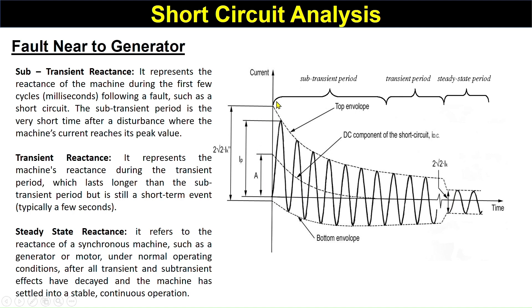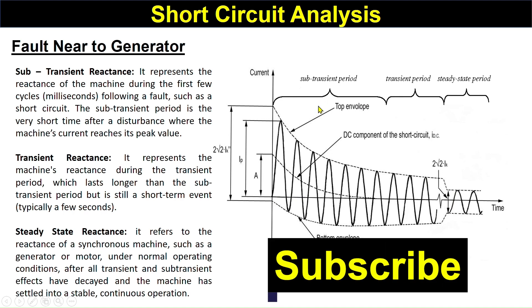The sub-transient period is the very short time of the disturbance where the machine current reaches its peak value. The transient reactance represents the machine's reactance during the transient period, which lasts longer than the sub-transient period — typically a few seconds — while the sub-transient period is of milliseconds duration.